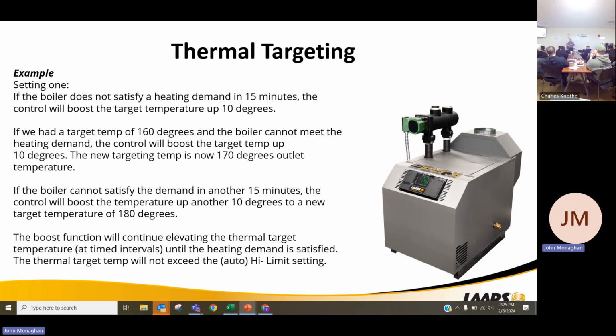Because again, when we go to do our heat loss or our system design, we're designing for our worst possible day. We're designing for 10 degrees. We're not at 10 degrees very often. We're designing for the worst case scenario. At 10 degrees, I need 180 degree water to heat that home. A day like today, I may only need 150, 160 degree water to heat that home. It uses a little bit less energy to heat to 160 than it does to 180.